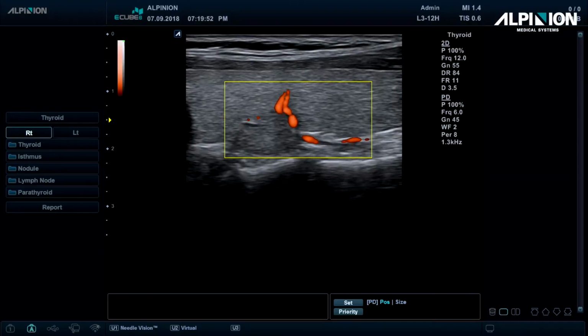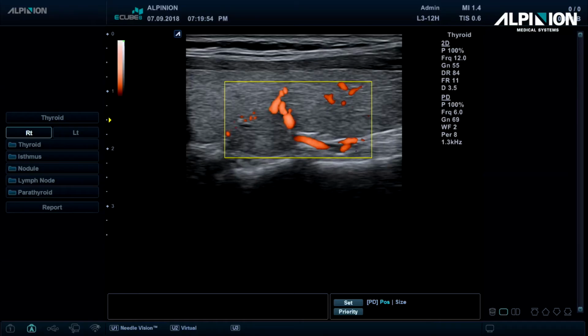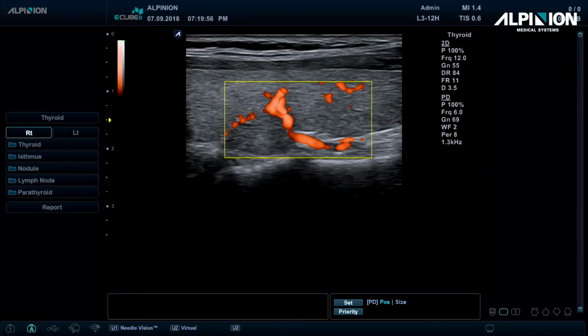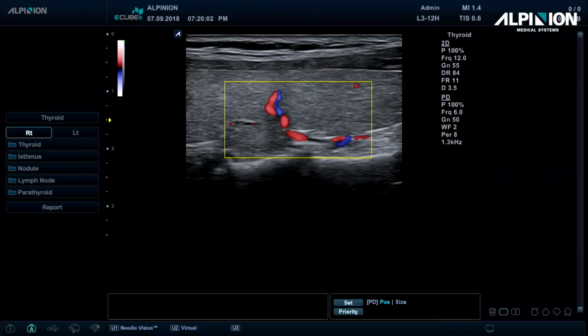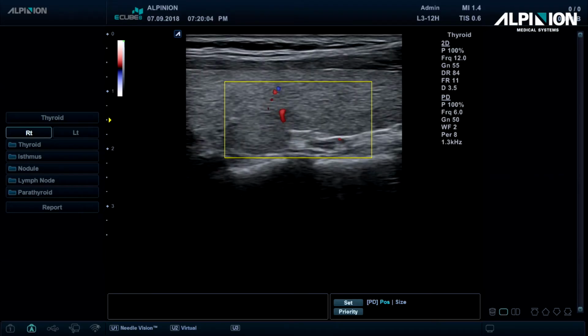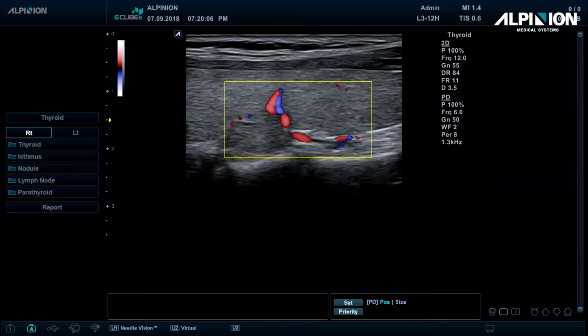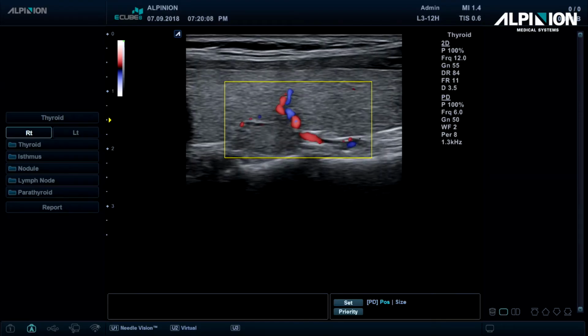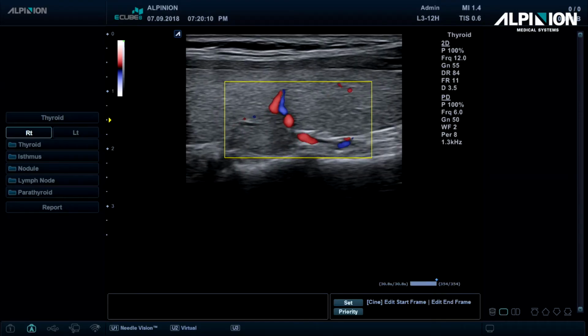By rotating the Color Flow button in the same way, the overall power Doppler gain will be adjusted. As you click a DPDI button on your touchscreen, you can activate this Directional Power Doppler mode. Then the single color of Power Doppler is changed to the two complementary colors indicating each different direction.